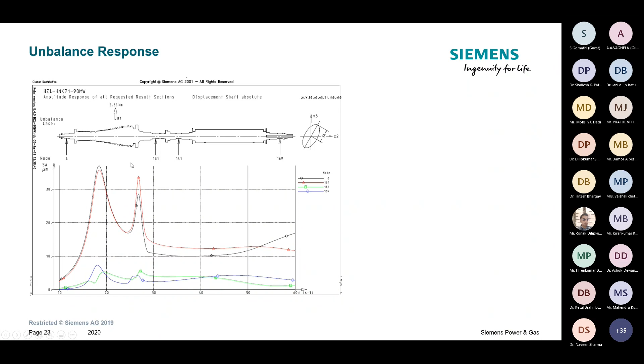So this is about the theoretical side, and the dynamics of the system almost all come from the fluid film, and even the steam valves. That means the steam also acts as dynamic damping, acting as a force on the rotor. The leakage from the seals also matters, because there is a very narrow gap between the rotating and stationary components, and there is a lot of turbulence over there, so they act as damping in the rotor, and a small change in the gap will change the entire behavior. So that is also very important. If I compare with a stationary component, we call it vibration: a spring mass system vibrating like this. But in a rotating system it's whirling.